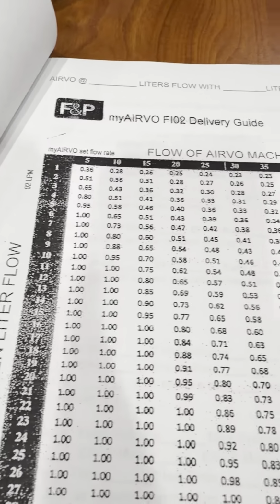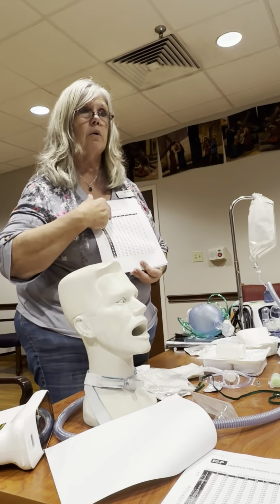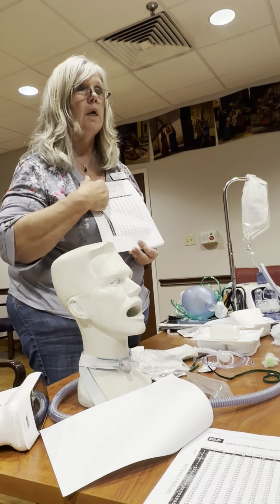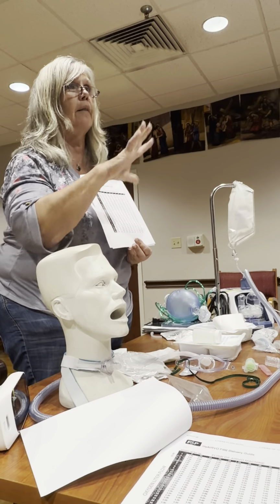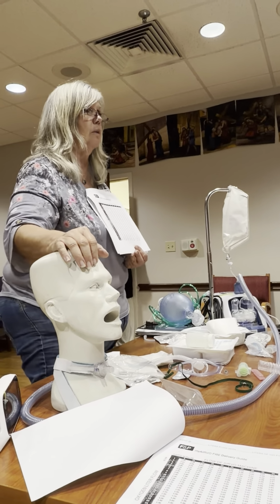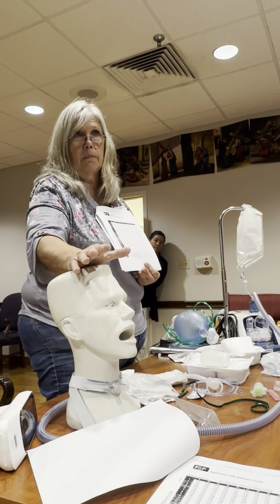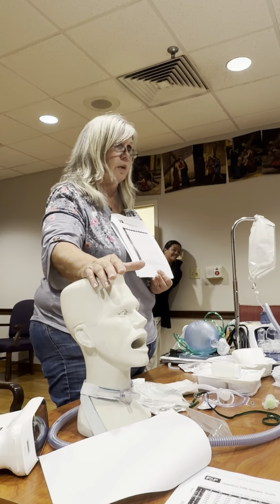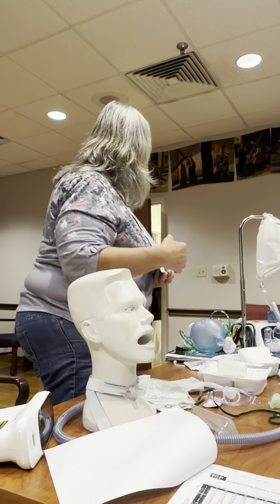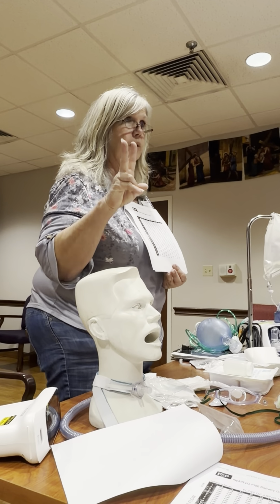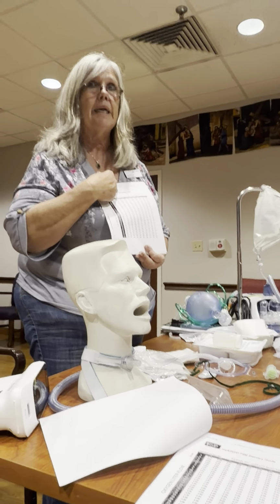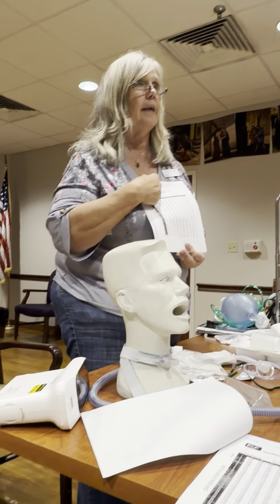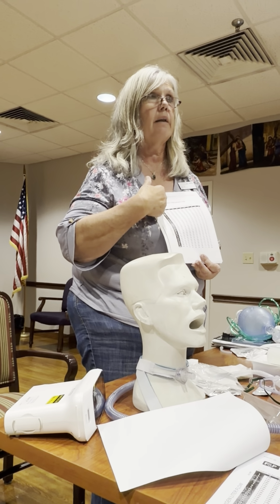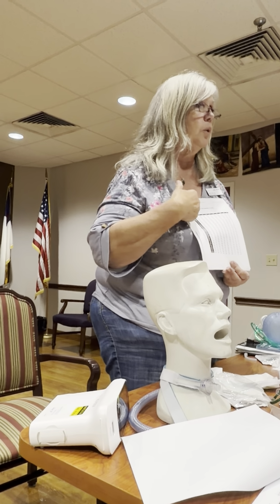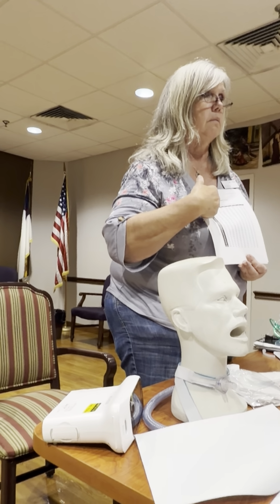So I always set the flow of the machine on 20. So I would go across the top and find the 20. So say they're on 28%. Now they may call from the hospital and say they're on 6 liters, 28%, and then you get in a panic mode because we don't have a 6 liter concentrator. And I say, no, you don't have to worry about it, it's only 2 liters. So when you find that 20, go down to the 0.28 and then come over on this side and it would be 2 liters. So, see what I'm talking about?